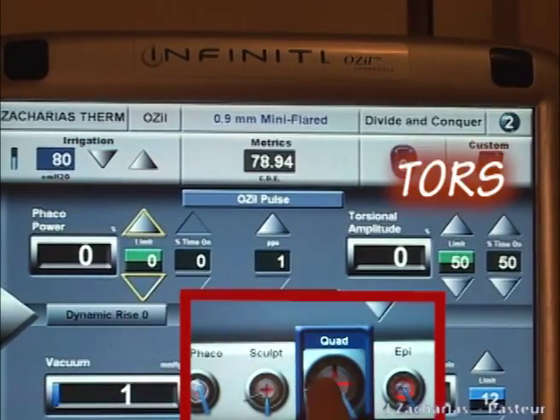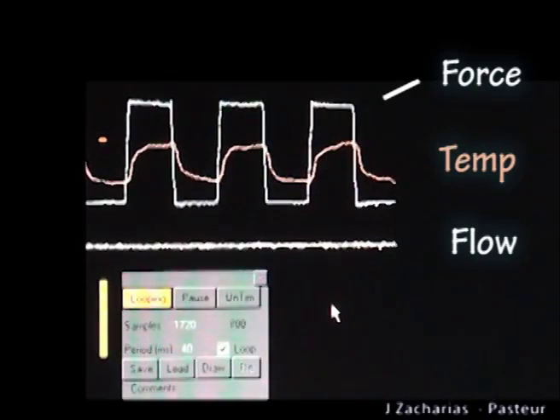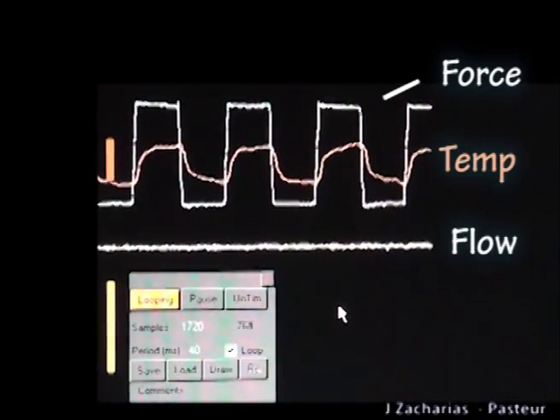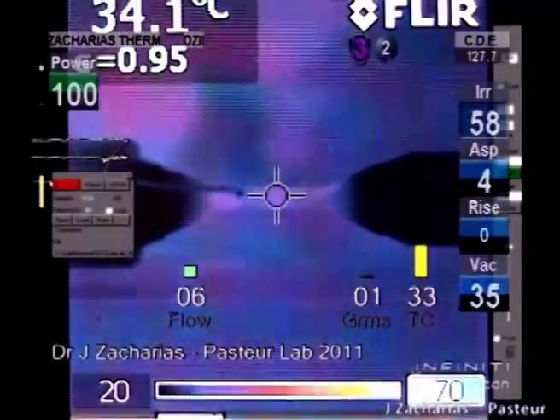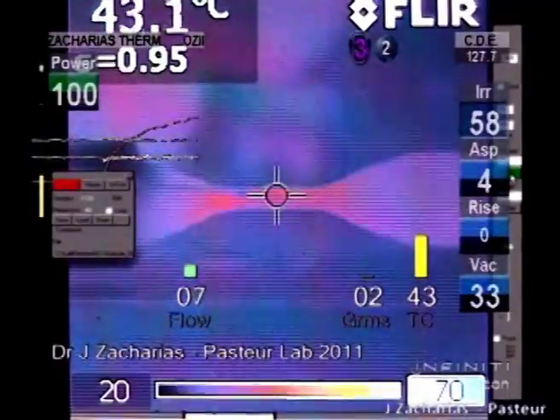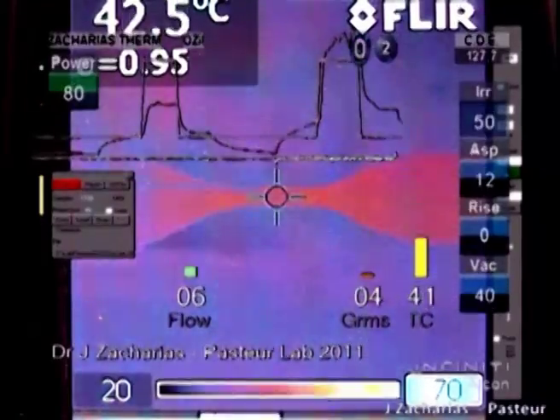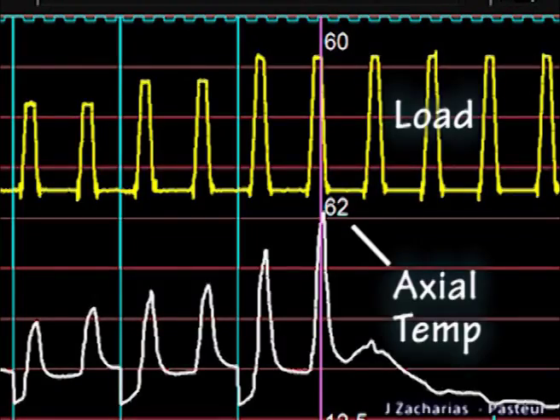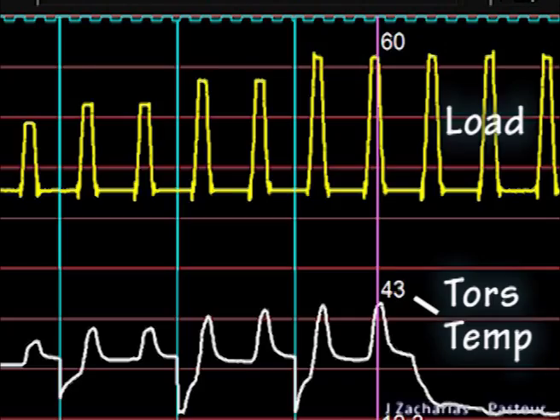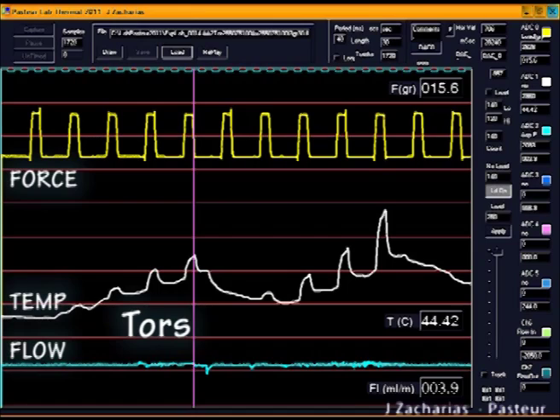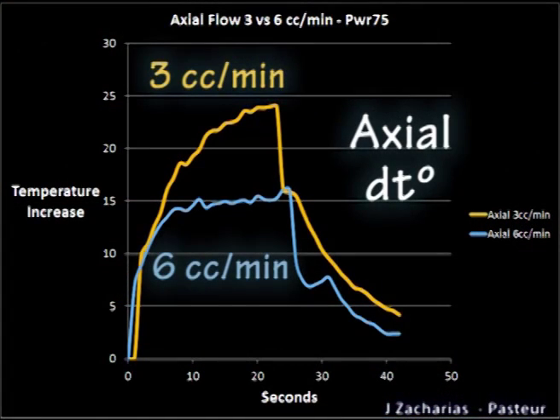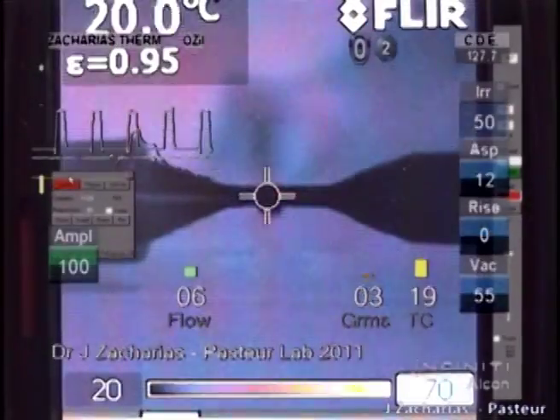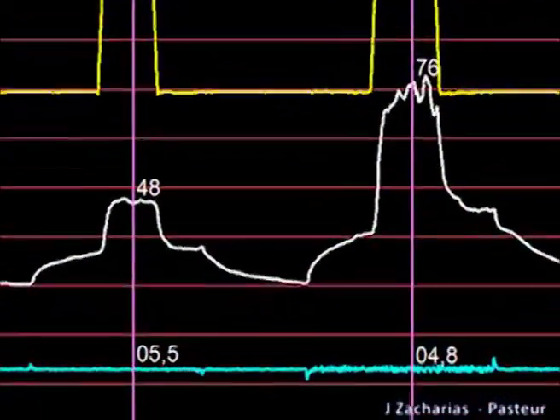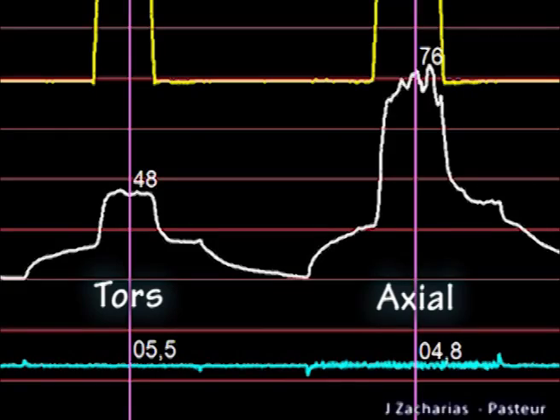Experiments were performed in sequences of axial and torsional power using load pulses of fixed magnitude and duration. Ultrasound activation produced an elevation in baseline temperature. Adding load produced a further increment in temperature that was more relevant with axial than with torsional. Increasing power produced more temperature elevation at the simulated incision location with axial. Low flow was associated with higher temperatures, also with axial. In general, for equal settings, axial produced more heat than torsional in the incisional area.